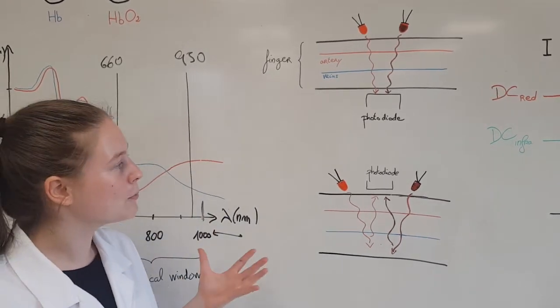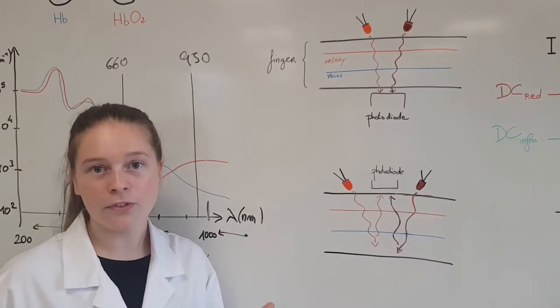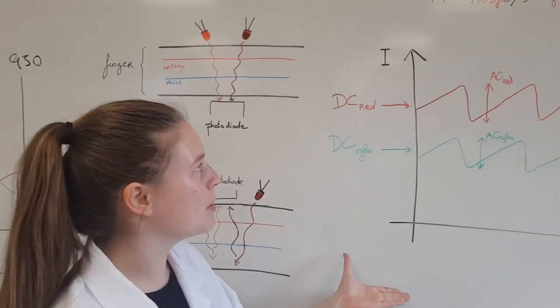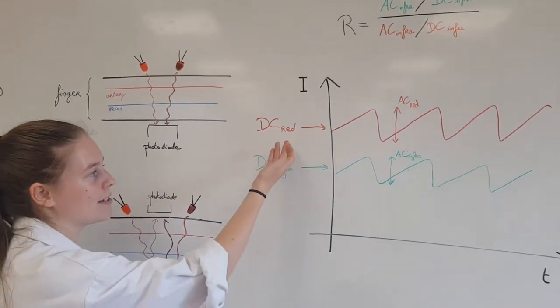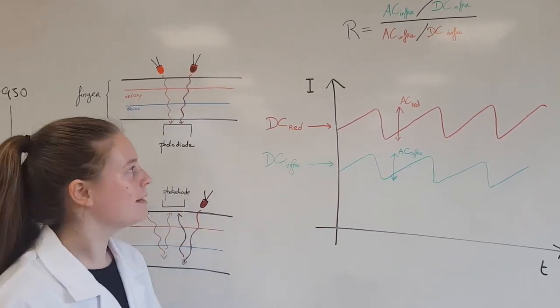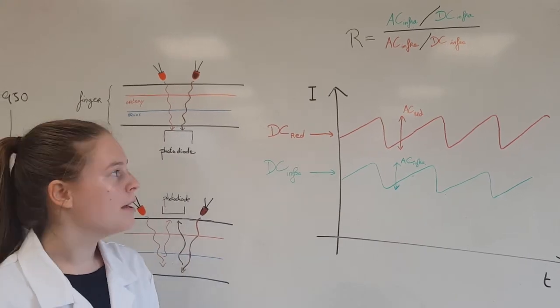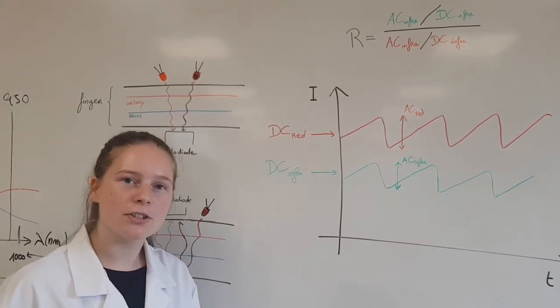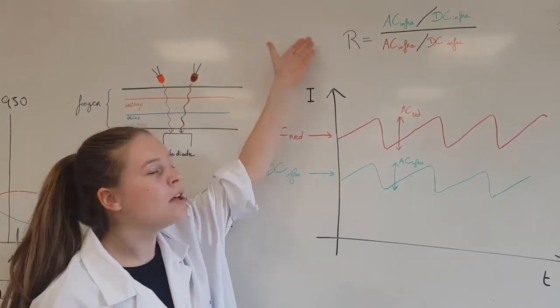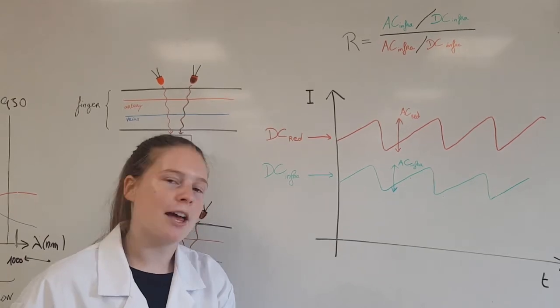The photodiode measures the light collected from each LED separately. Here is a representation of the signal we can obtain for each LED: the red light and the infrared light. DC components correspond to the average light intensity transmitted, and AC components correspond to the variation of light intensity collected during each heartbeat. Making a ratio of these measured values enables us to access the oxygen rate of the patient's blood, which should be around 98% for a healthy patient.